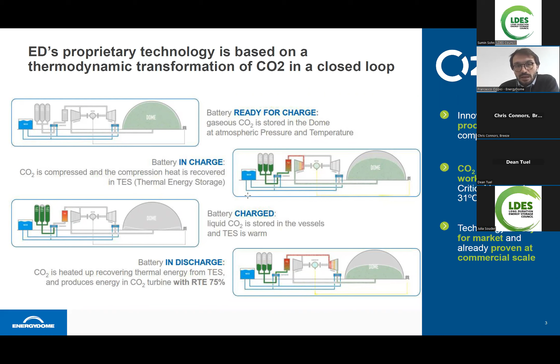Currently, Energy Dome is commercializing our standard module, which is a 20 megawatt, 10-hour duration system, actually 25 megawatt on the compressor and 20 megawatt on the turbine. This kind of compressor and turbine are exactly the same type that we have used in our commercial demonstration project. All of the equipment we deploy is actually available from tier 1 reference suppliers, which are not only ready to supply this equipment, but also guarantee its performance.